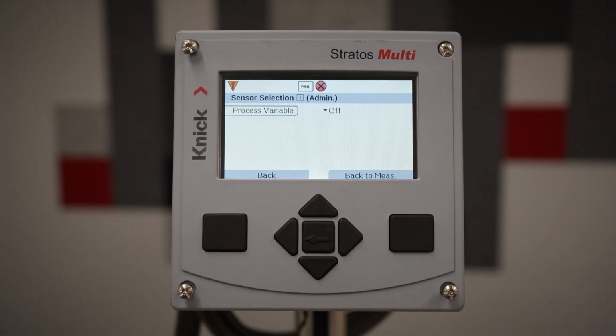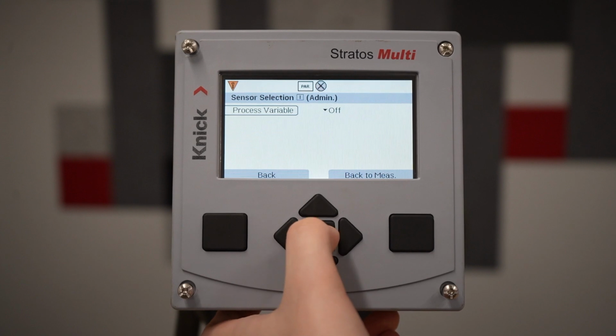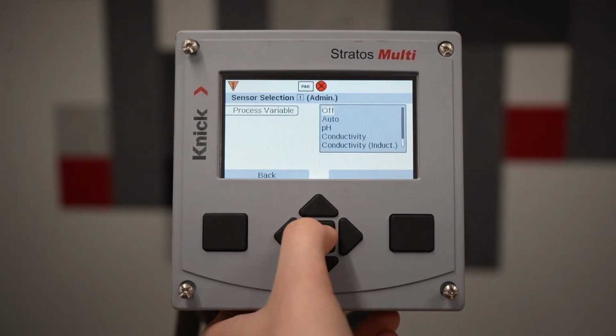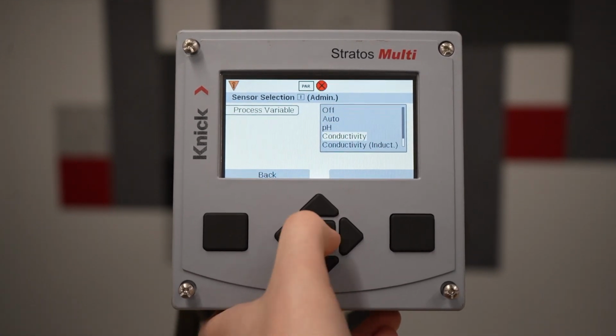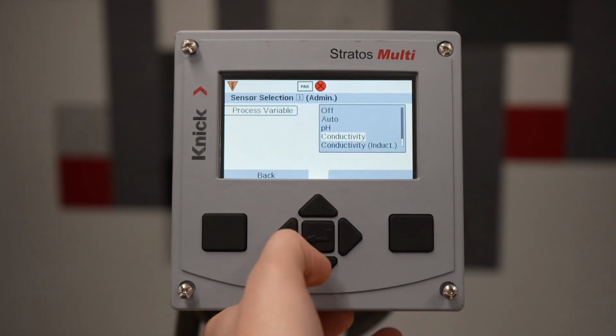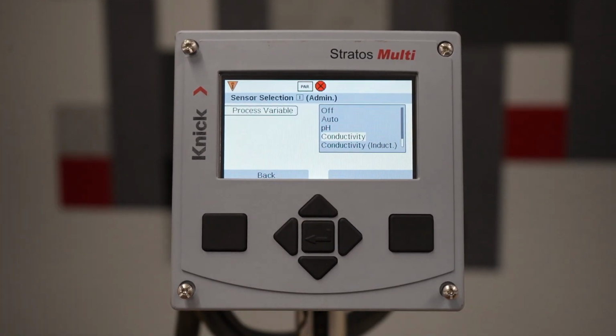This might be on or off for you, but for example, if we're using an ultra pure water sensor, I'm going to go from off, and specifically select conductivity. If you have an inductive conductivity probe, you would select that, but here we have a normal conductivity probe.